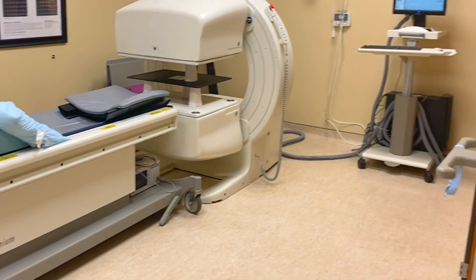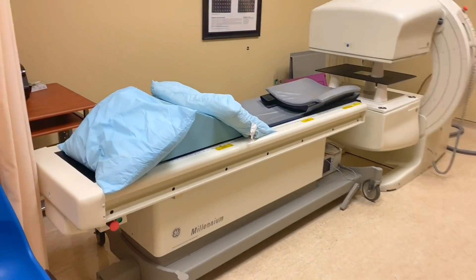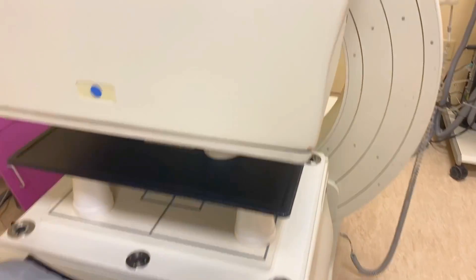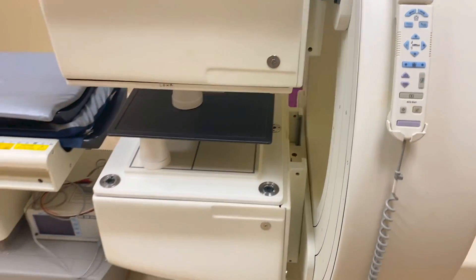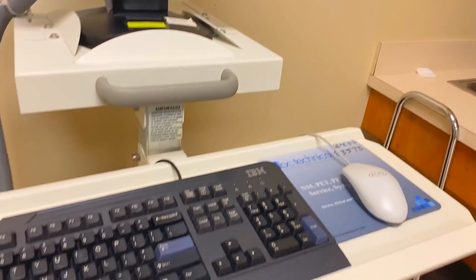This is a small facility, so everything nuclear medicine is in one room. I've got my gamma camera in the same room as my hot lab. My gamma camera is actually a GE Millennium — it's not my favorite, but it's really not a bad camera at all. Right now I'm showing you that I'm doing my daily floods, which is just a radioactive source, and it actually looks like this.